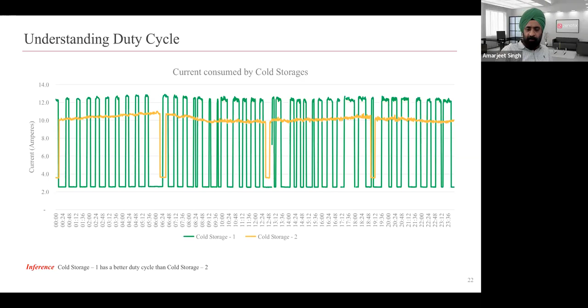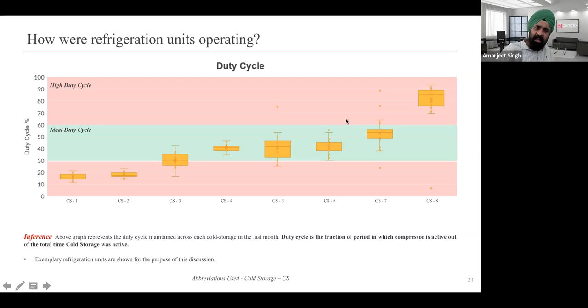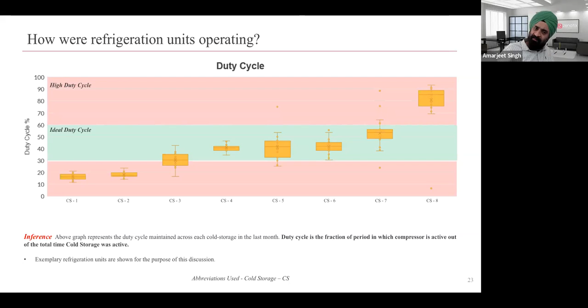So you can see CS3 through CS7, their median values are in this ideal range. CS3 is barely in that ideal range, while CS1 and 2 have very low duty cycling, and therefore it is resulting in both energy wastage as well as perhaps the equipment health not being good. And CS8 is showing very high duty cycling, and that again may lead to the equipment eventually getting conked off, right? So these are the examples of how we get into the asset health monitoring.